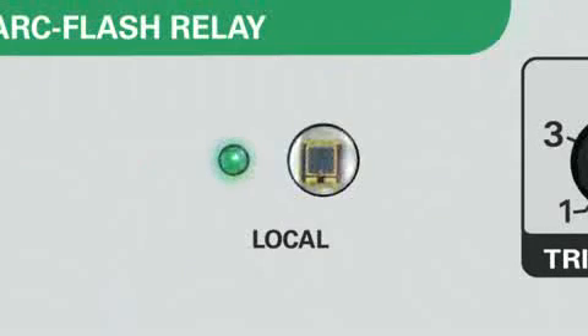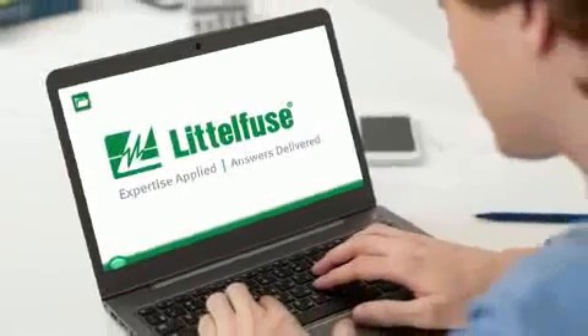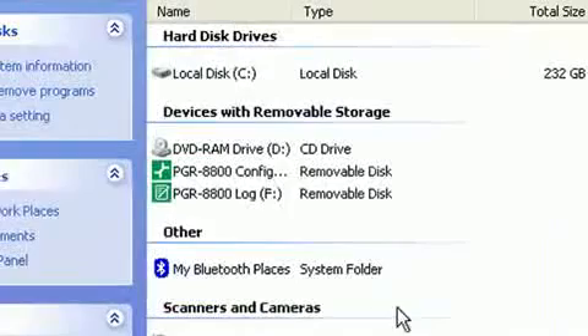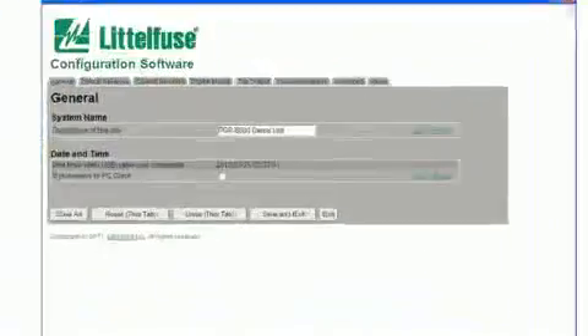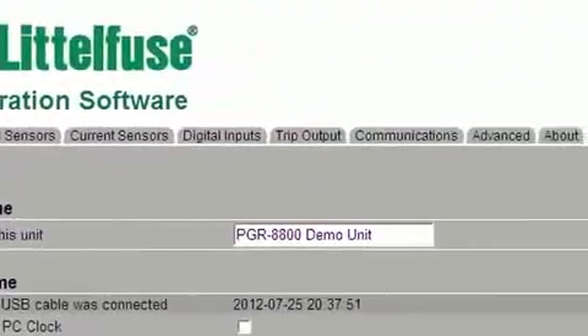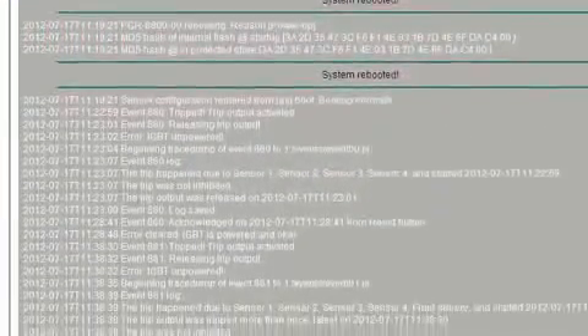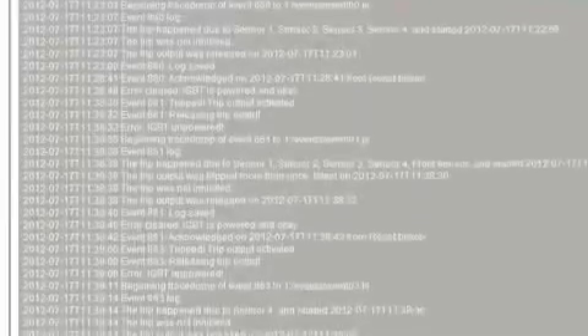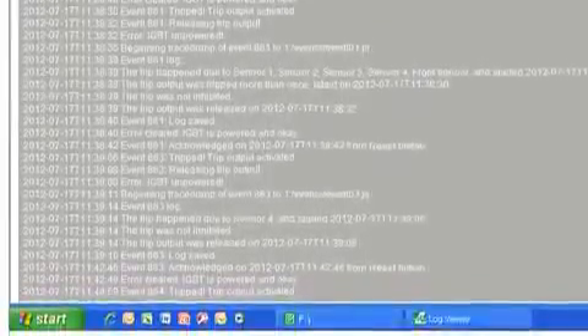When you connect into the USB port, the software and device drivers automatically load into your computer much like a jump drive would. So you can do your initial setup from there, but you can also view the currents for each phase at the time of a fault. You can also see the intensity of the light at the time of the fault via our event logger.